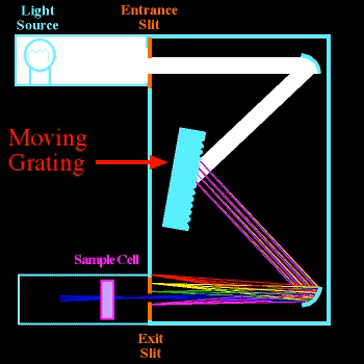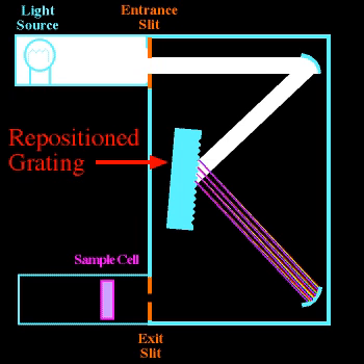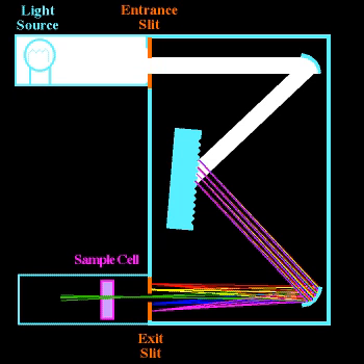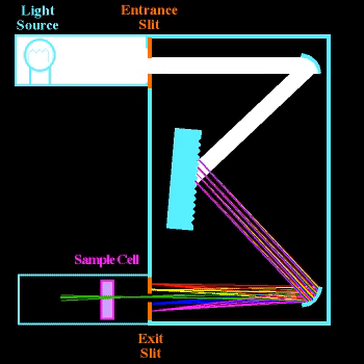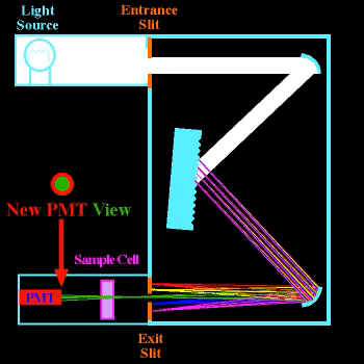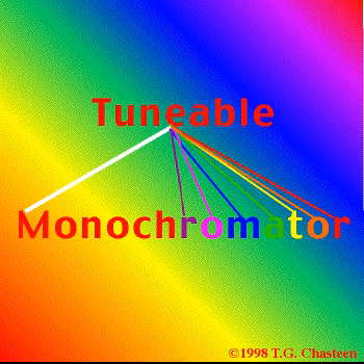The second tuning step shows a slight adjustment of the grating position, controlled by computer in modern instruments, which changes the reflection angle of light rays striking the grating. This translates to a different position of wavelength bands at the exit slit plane. Here, the monochromator has been tuned to allow 500 nanometers, that is green light, to pass through the exit slit while all other wavelengths, including the 425 nanometer blue light from before, are blocked. The PMT now detects the 500 nanometer light's intensity. Analyte content is determined by a calibration curve plotting absorbed light at a specific wavelength versus known analyte concentrations.